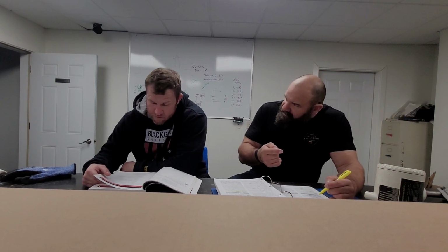Let's go back to the previous question. There's accessible as applied to equipment. There's accessible as applied to wiring methods like Romex and stuff. And there's accessible as applied to readily accessible. So readily accessible means capable of being reached quickly for operation, renewal, or inspections without requiring those to whom ready access is requisite to take actions such as use tools other than keys. That's highlighted, so that's a new addition to the code. Climb over or under, remove articles, or resort to portable ladders and so forth.